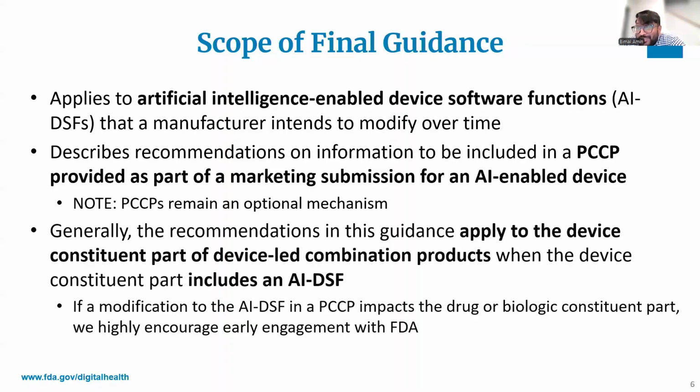Please note that PCCPs are optional and a tool manufacturers can use when they anticipate needing to update their device over time without submitting a new pre-market submission each time. Lastly, for combination products where you have a device component that also involves a drug or biologic, the guidance generally applies to the device constituent part. But if a modification to the AI component would impact the drug or biologic side of the product, we strongly encourage you to engage with the FDA early. Don't wait until you're ready to submit and come talk to us first.